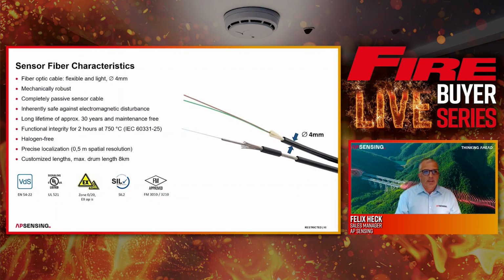The sensor cable itself has a very long lifetime of 30 years. The sensor cable itself is maintenance free. You cannot open it, you cannot look at it. It doesn't make sense. From time to time, you have to have a look if the sensor cable is still in position, and then everything is fine. Functional integrity of 2 hours at 750 degrees. That means that we can measure throughout the whole fire incident, and provide the data to the investigation police also for the investigation later on.